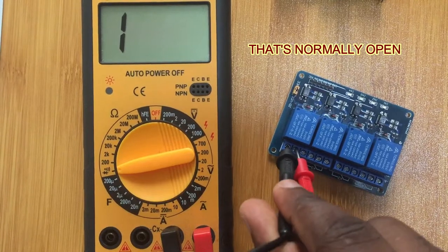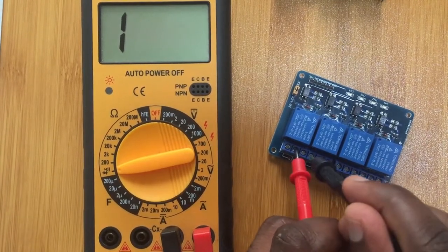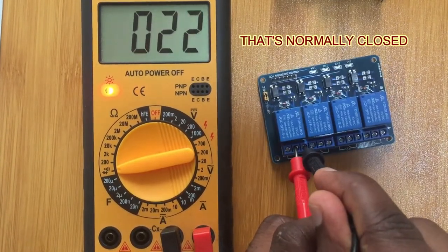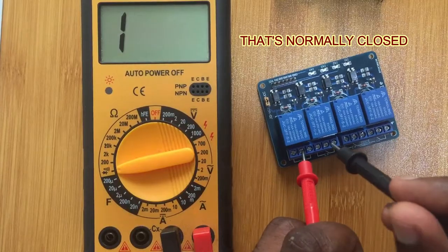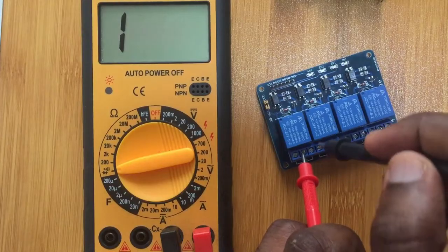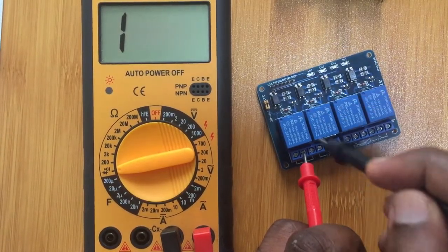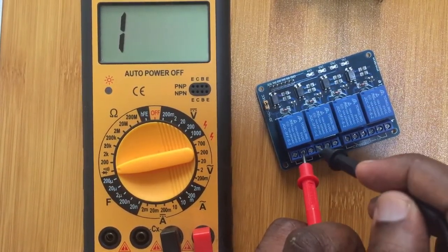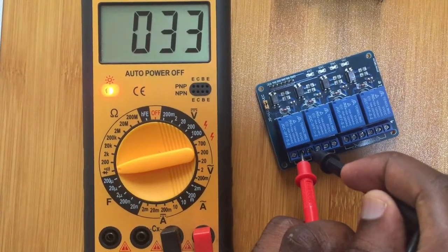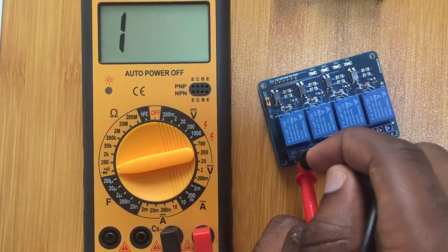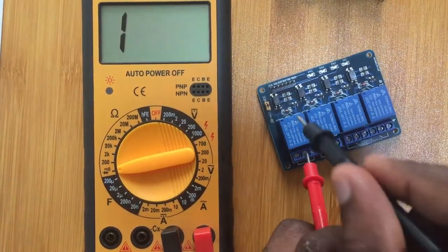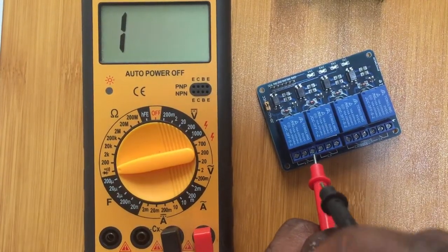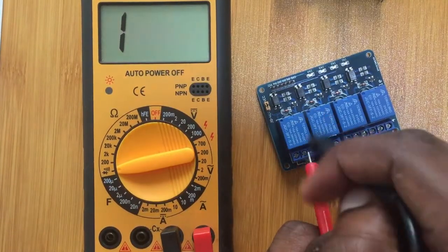When you put here, it means that is the normally closed terminal. So the normally closed terminal means even if there is no signal or there is no current through the relay, these two terminals are connected, while this one is not connected. It only gets connected when there is a signal or current through the relay.